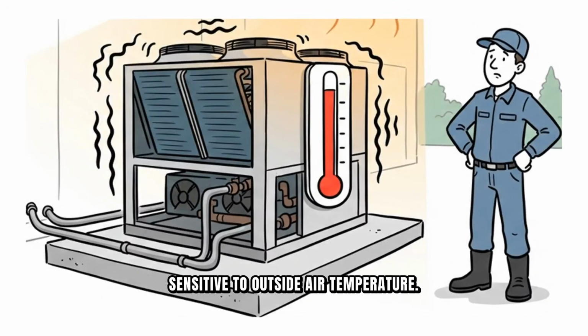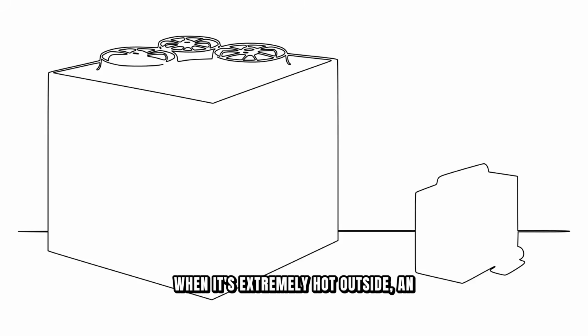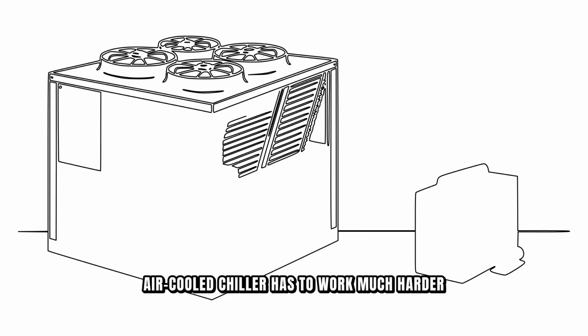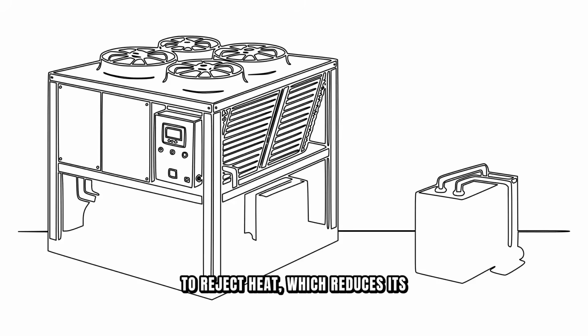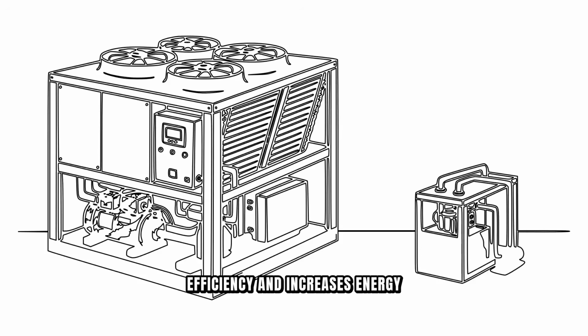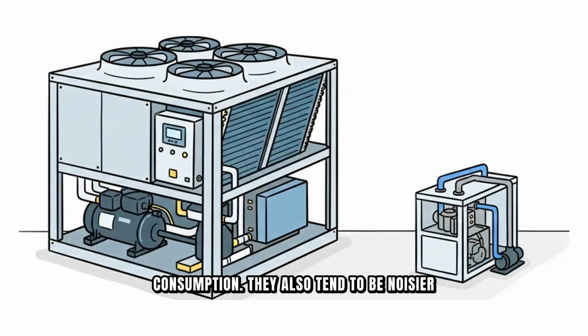However, they're sensitive to outside air temperature. When it's extremely hot outside, an air-cooled chiller has to work much harder to reject heat, which reduces its efficiency and increases energy consumption. They also tend to be noisier than water-cooled units and take up more physical space because of their large fan systems.